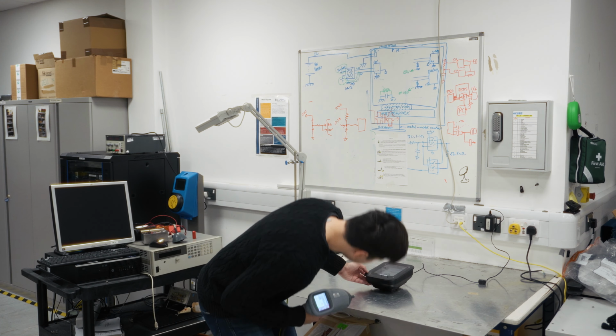Now I can access the conductive surface of the DUT on the back, and I'm going to apply 4 kilovolt contact discharge into it, while also looking at the monitor to see what's happening. I'm not going to record this on my camera because that's impossible.